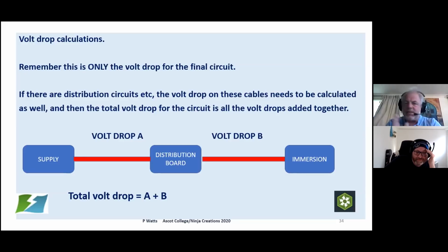So yeah, for dead tests, we want to try and eliminate them so that the calculation values mean something. For live testing, we need to have them in there so we know how the installation is going to react, as installed. It's a case of both scenarios. Yeah, it's a case of using your electrical knowledge and know-how and thinking, hang on, how is this going to work? Oh yeah, I really need to have that.